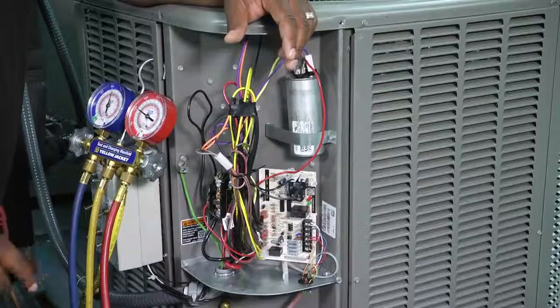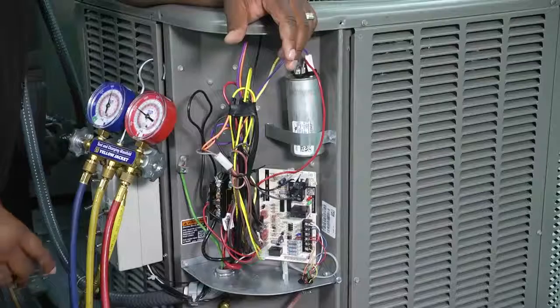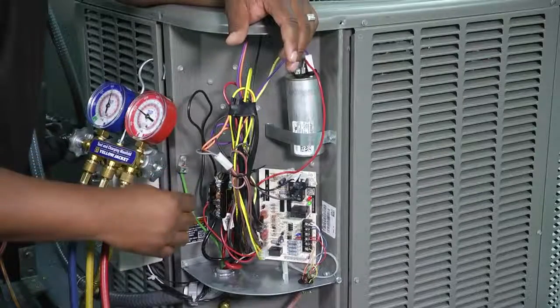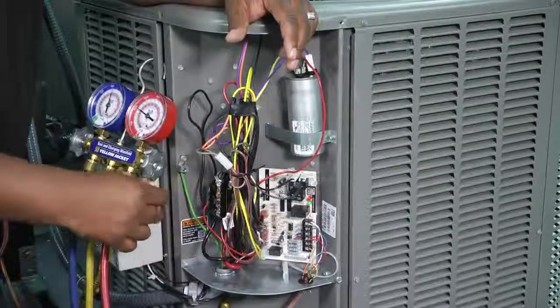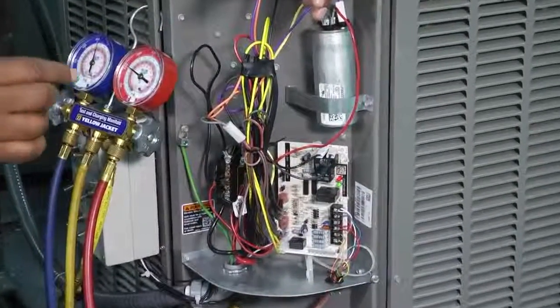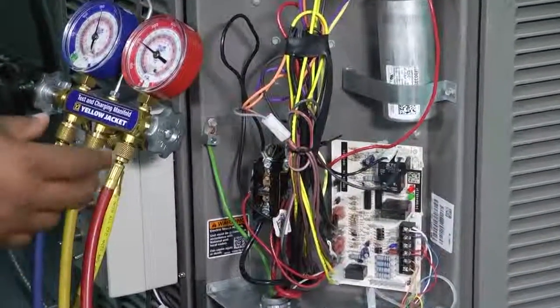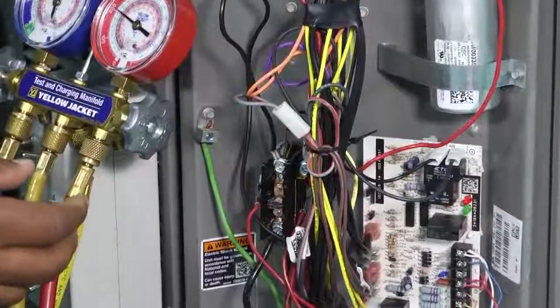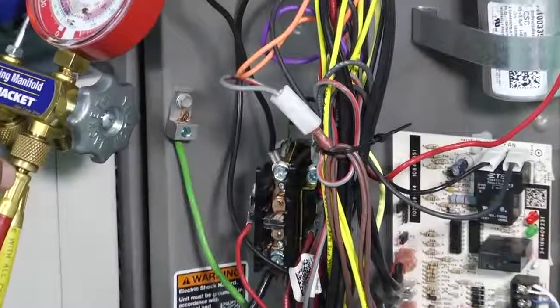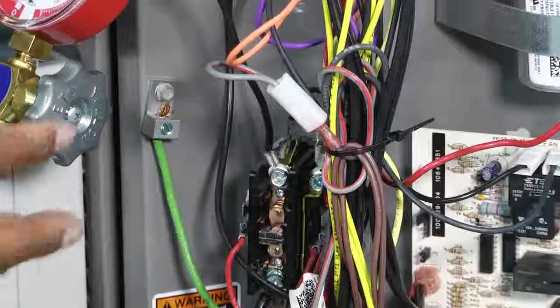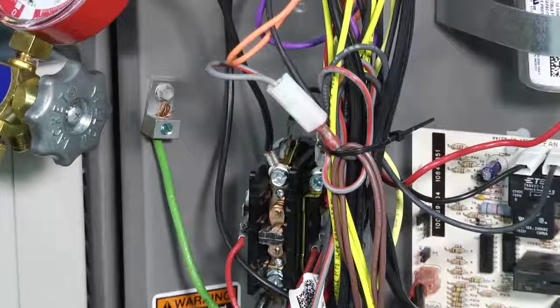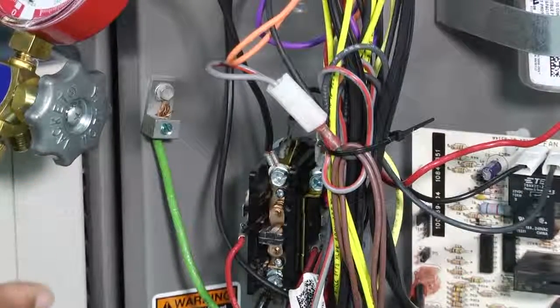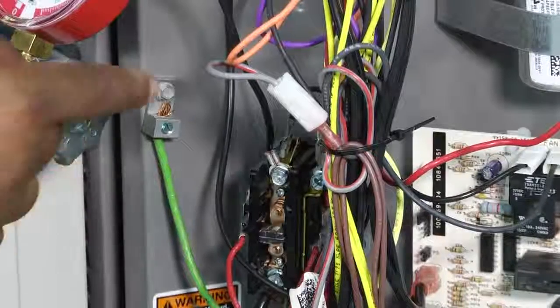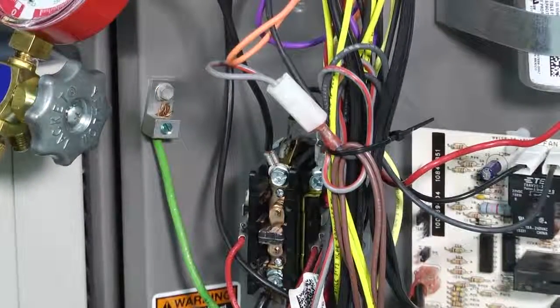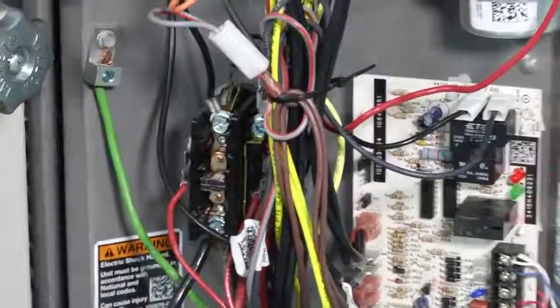A term that you'll hear in our industry a lot is the term pitted as it relates to contactors. And when you look at it, you'll see a lot of blackening from arcing of those contactors hitting or chattering together. And if that happens and it becomes too much of a buildup there, then those contacts won't make contact and our contactor won't be able to do its job and actually allow our unit to come on. So you need to check the integrity of our contactor. Another item that you'll check is your capacitor.